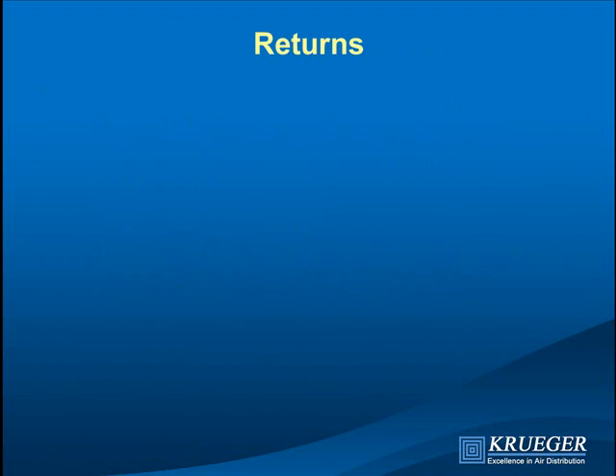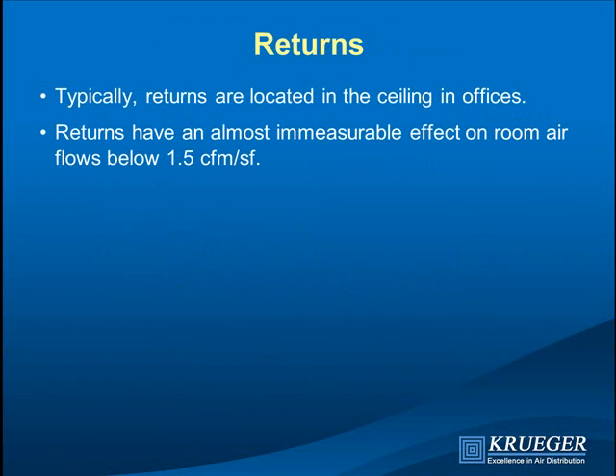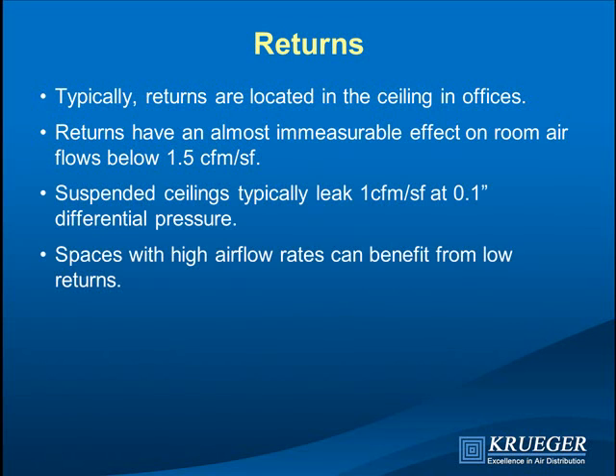People often ask where to place returns. The answer is: it doesn't matter much. Ceiling returns have an almost immeasurable effect — you can place a return right next to a supply diffuser without affecting its performance. Suspended ceilings typically leak a lot, so air will exit the room regardless. If airflow exceeds 1.5 CFM per square foot and you have a heating problem, low returns could help, though they are usually not convenient.